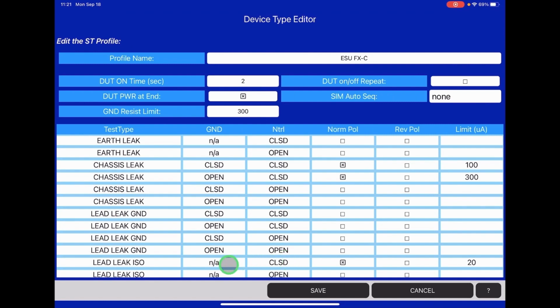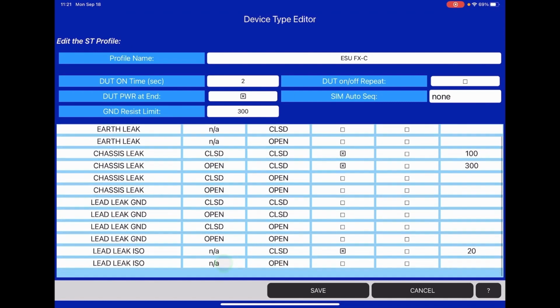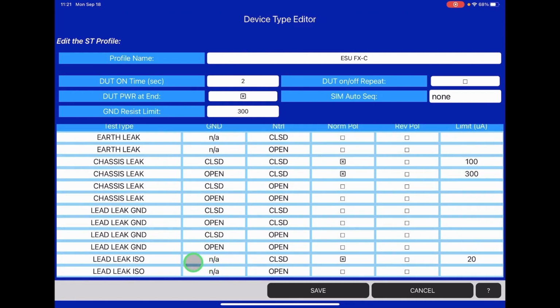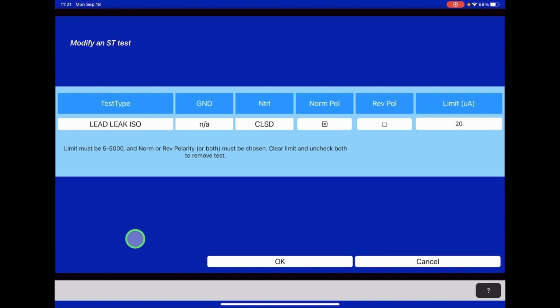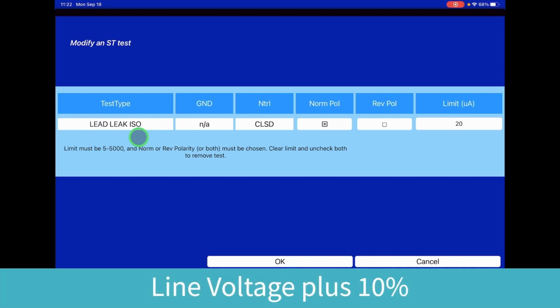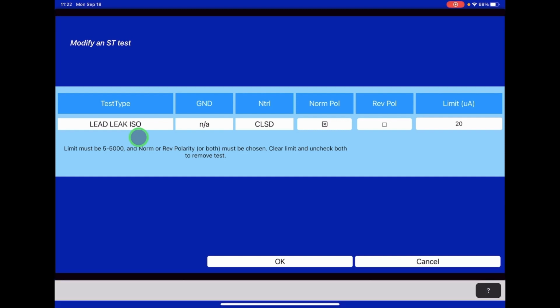That's the second test, and then the third test is an output channel test, and we're going to go ahead and run a lead leakage, what they call sink current test, which in terms of the safety analyzer, that's running an ISO test, or it's also commonly referred to as a MAP test, a mains applied parts test, where you're applying 120 volts AC to the analyzer to verify how much current it sinks.